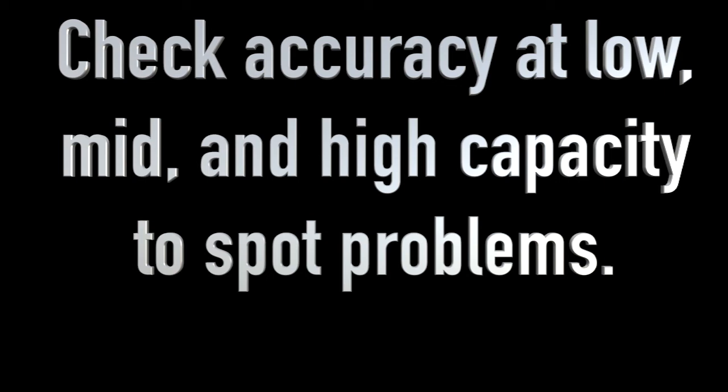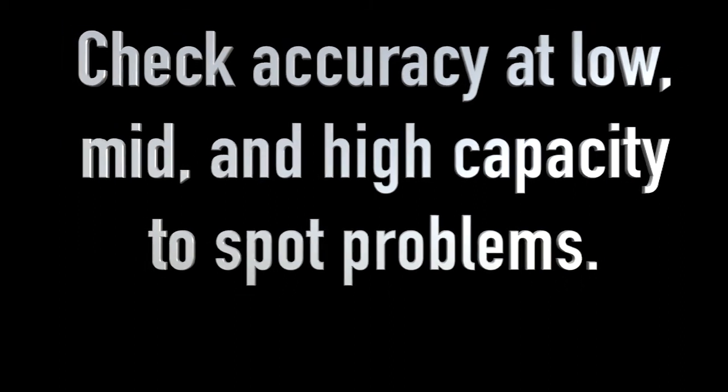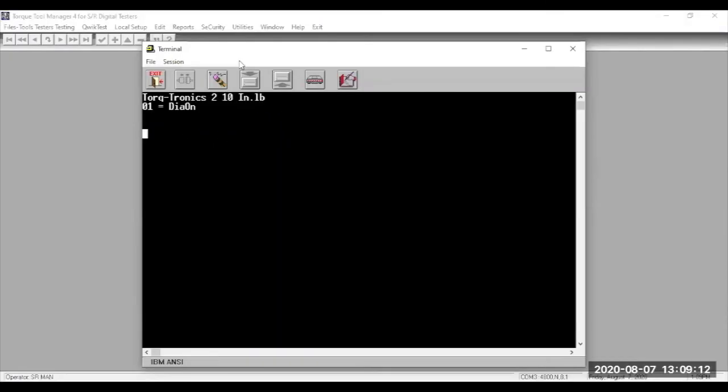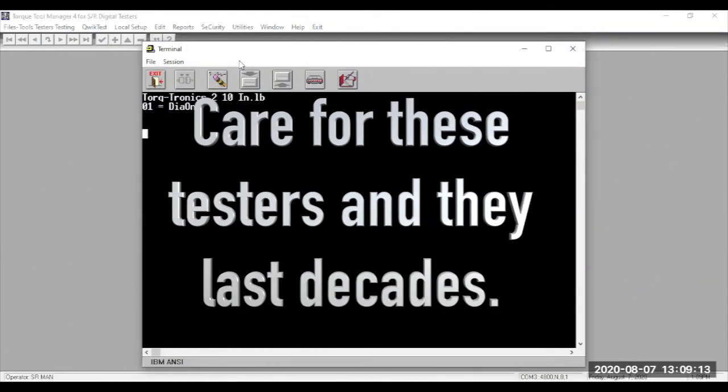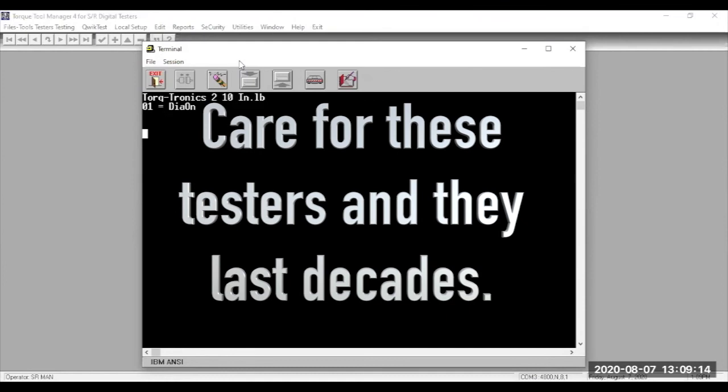If the offset is 3% or more, you may want to consider sending the tester into the factory to have it checked out. We can repair or replace the transducer as needed.